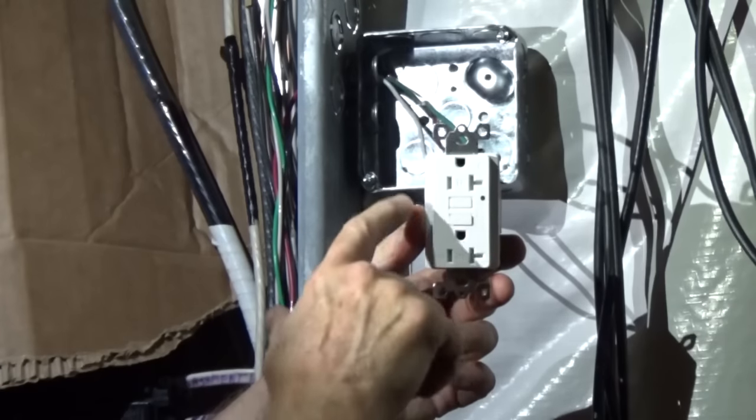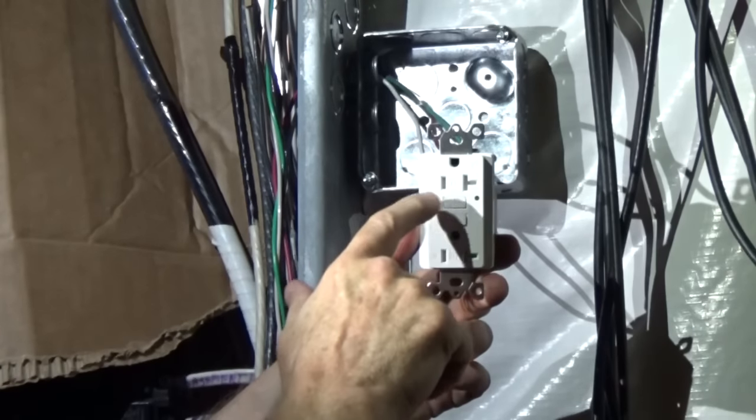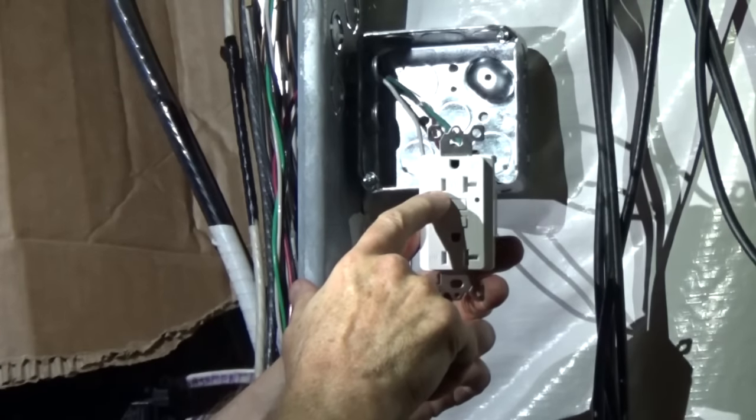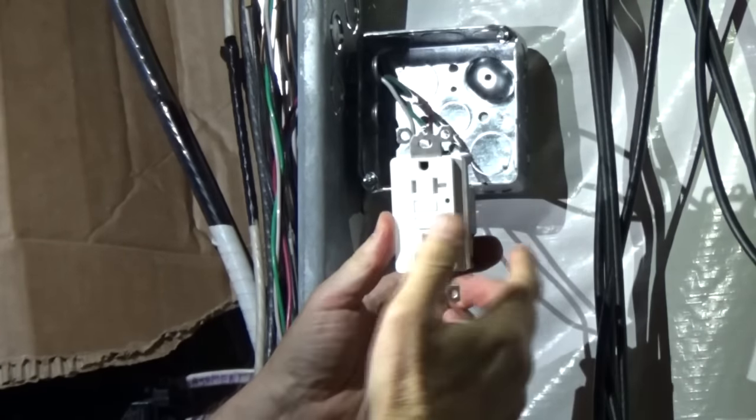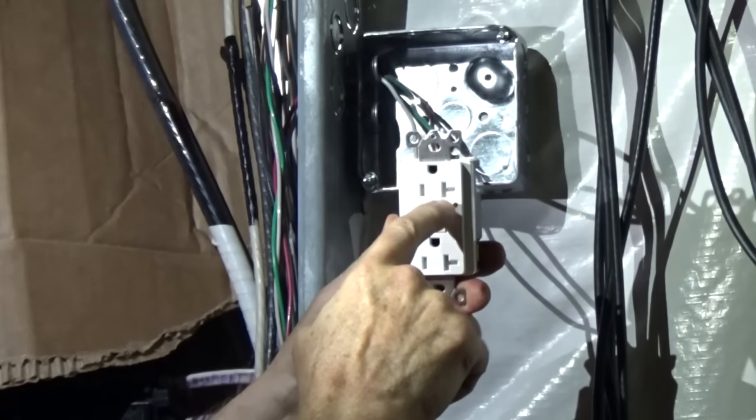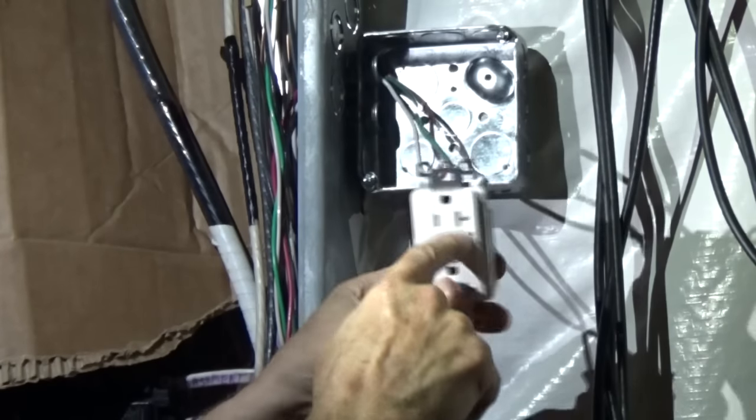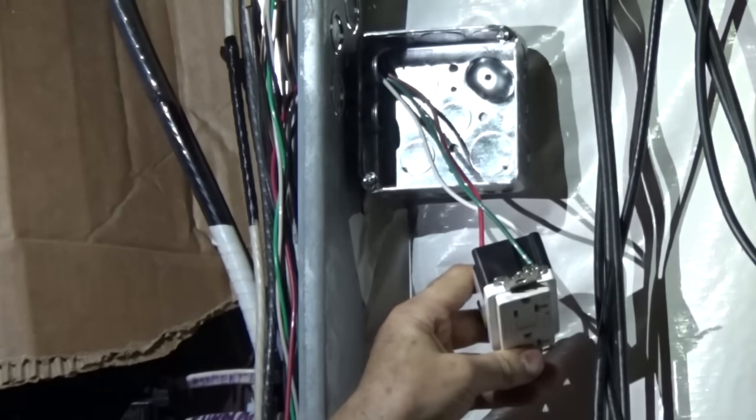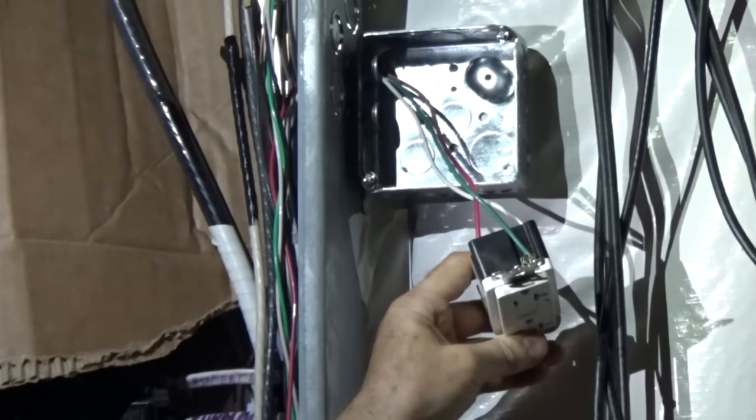Connect your hot wire to the brass screw, the side with the narrow slot, your neutral wire to the silver screw, the side with the wide slot, and your ground to the green screw.